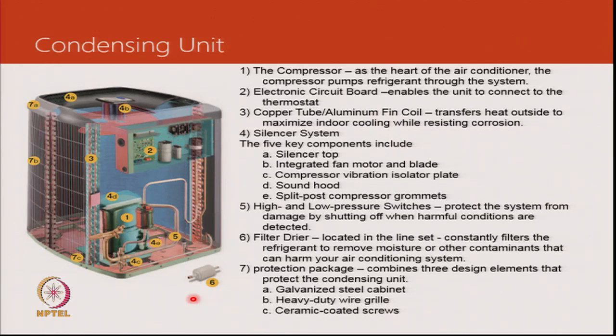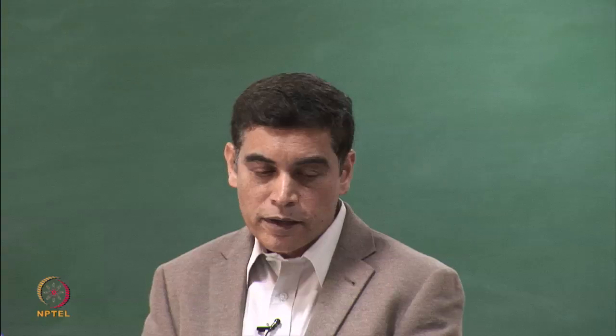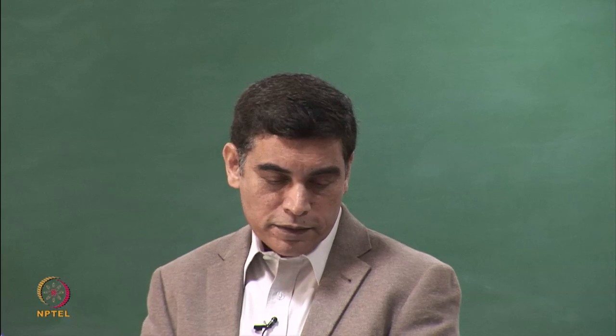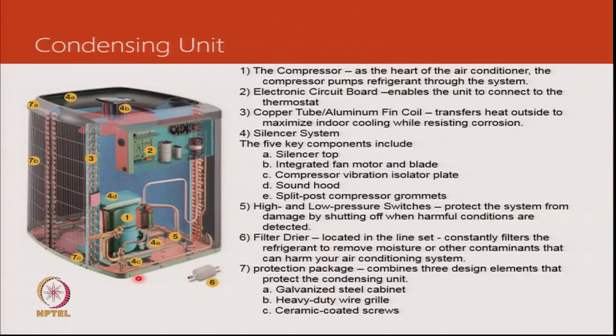So in a condensing unit, other than the coil, we will need some means of mitigating any additional noise, and then some pressure switches if it is a large condenser, to protect the compressor from operating outside its design limits. We would put in sensors that would signal the controller to switch it off if there was any untoward thing. And things that we need to be aware of is again clogged coils, refrigerant leak, high discharge gas temperatures, and all that. In terms of choosing materials for making a condensing unit, we would look at corrosion resistant steel. So galvanized steel would be a common choice, and then we would look at powder coating it. We would look at shape so that there is a certain quality of manufacturing that is possible.